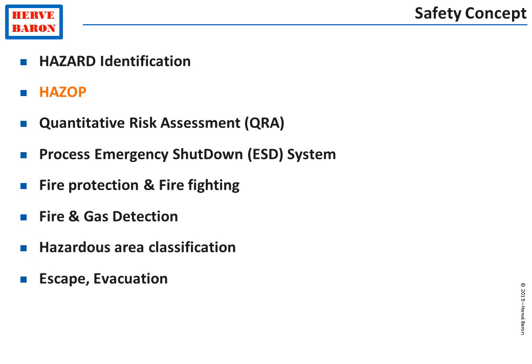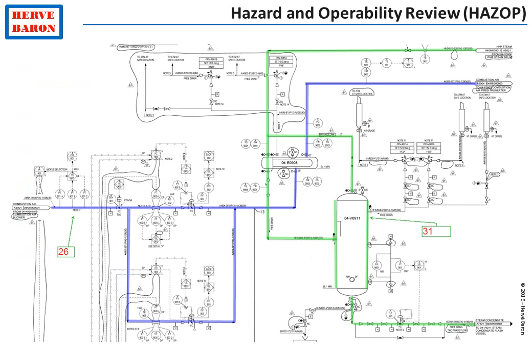The HAZOP, which we have already mentioned in relation to P&IDs, is a systematic review of the potential deviation of process parameters beyond their normal values. Is there a possibility, for instance, in the process line, for the pressure to deviate beyond its normal operating range? Such a possibility may be the failure of process controllers, failure of equipment, or operator error. If there is such a possibility, then the HAZOP will review whether there is a safeguard against this too-high pressure.